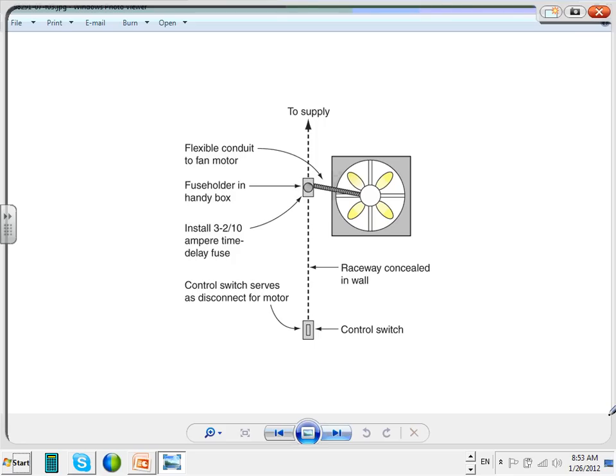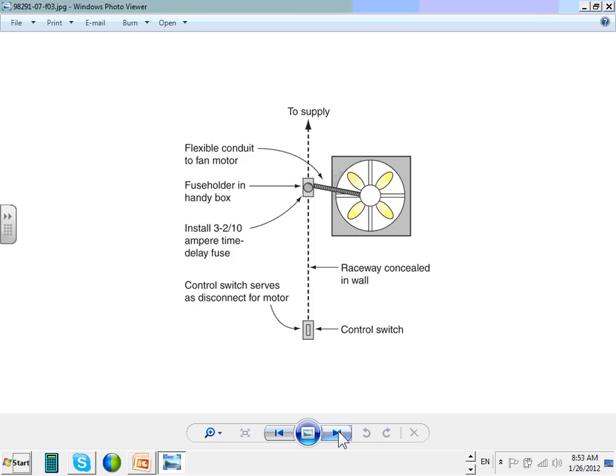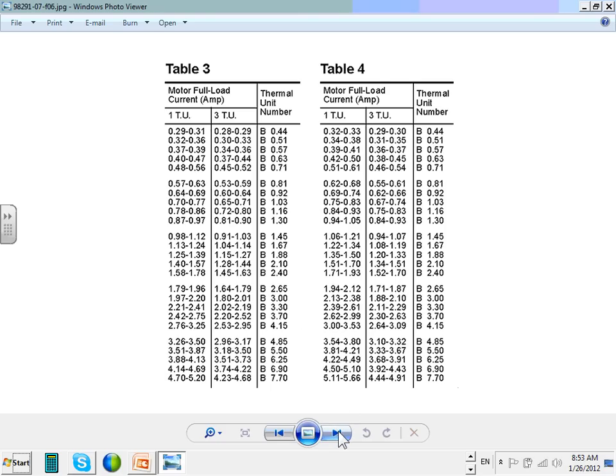If I have a 3-phase piece of equipment, most likely it's going to be 2, 3, 4, or even 5 horsepower or higher, and then you're going to have that one on the wall. So these are just the fractional horsepower motors where we can use snap switches. This is a list, guys, of overload sizing. I don't go over this with the designers.